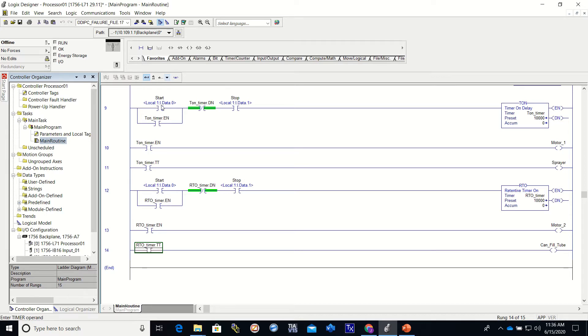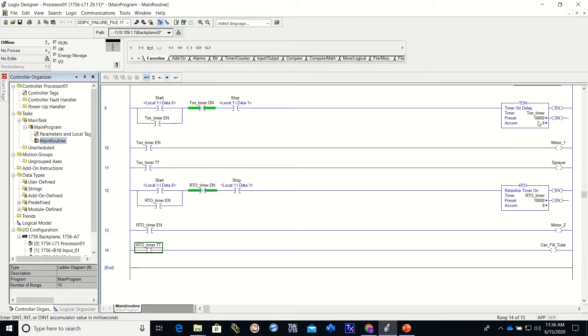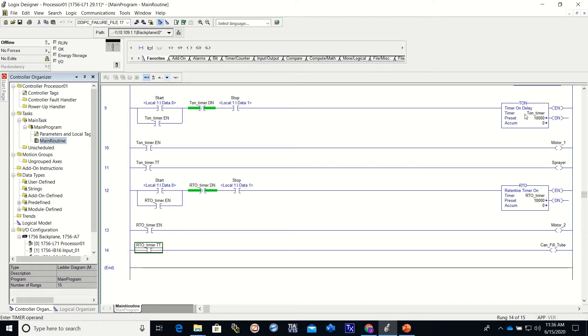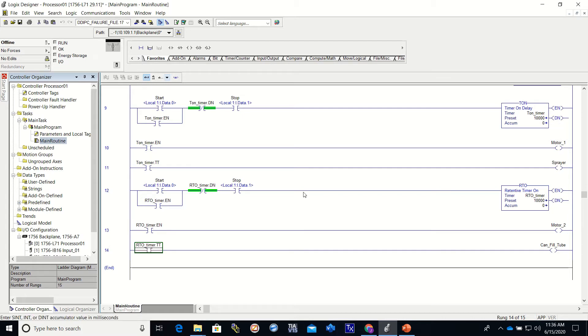So in this one right here, if we press the start and the TON timer is not done, the stop is made because it's a normally closed push button, then the TON timer will start timing and it will time for 10 seconds. We will get the enable, we will get the timer timing. When it's done, we will lose this, which means that the timer will lose this and the timer will reset itself.